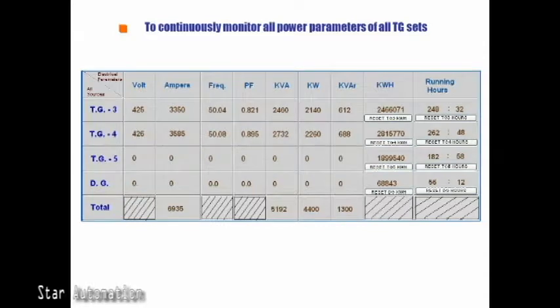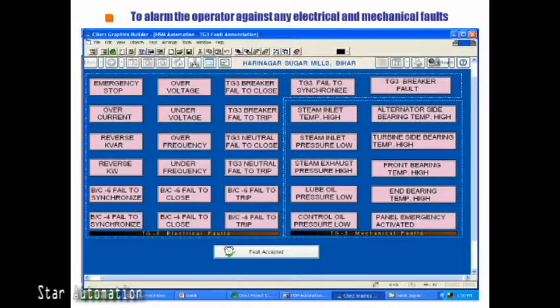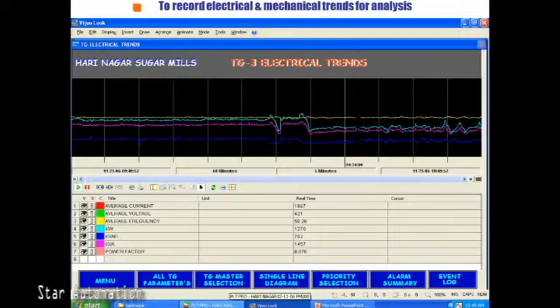Let's see the various SCADA screens of the powerhouse automation. This is the electrical parameters monitoring screen along with running hours display. The update time of the screen is one second, matching the update rate of the power analyzers communicating with the PLC. All these parameters are also recorded to the hard disk of the computer for historical trends display.